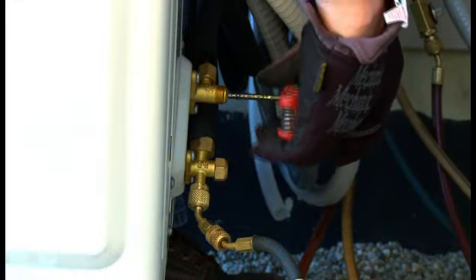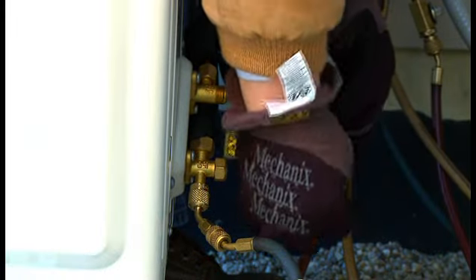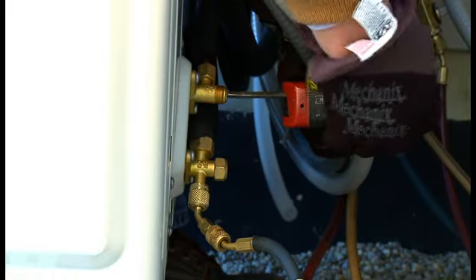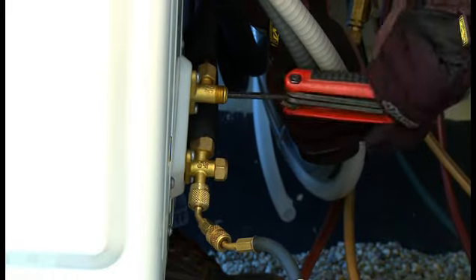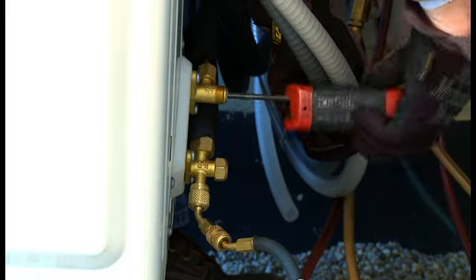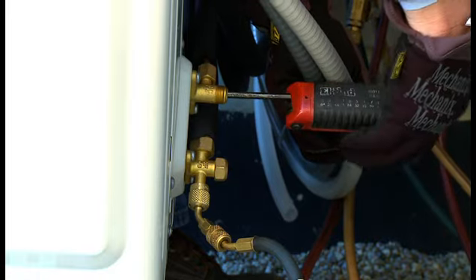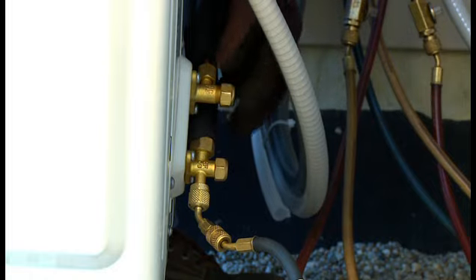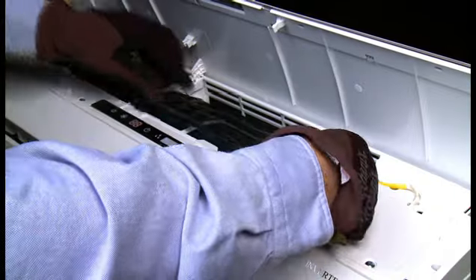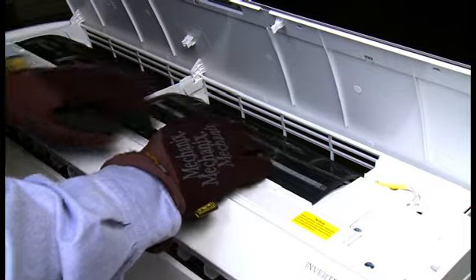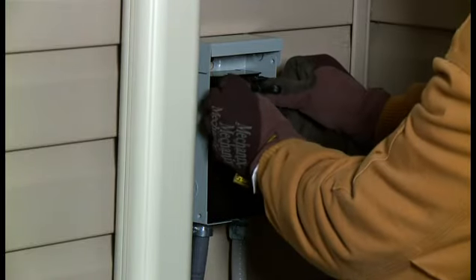Using an Allen wrench, open both valves to release the pre-charged R410A refrigerant into the system. The sound of the gas flowing into the system is heard, indicating refrigerant is charging the unit. Replace the sealing cap. Remove the adapter. Before testing the unit, make sure the air filter is installed. Begin the test by powering up the exterior unit.